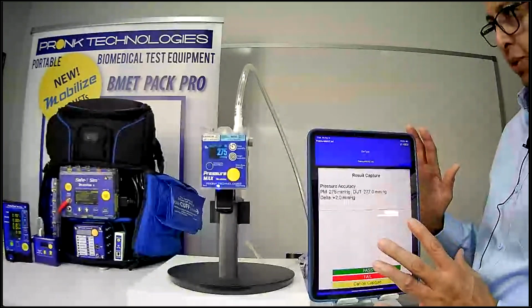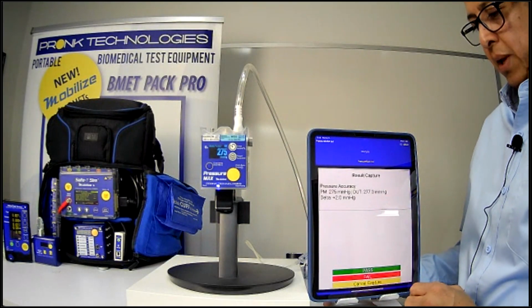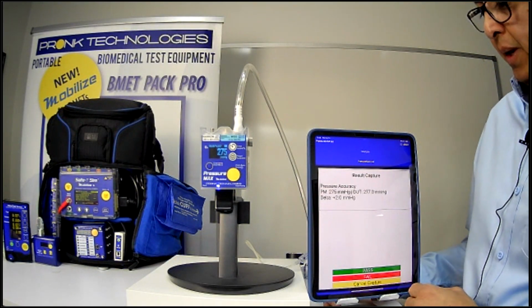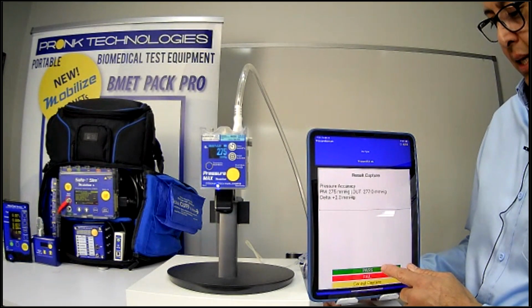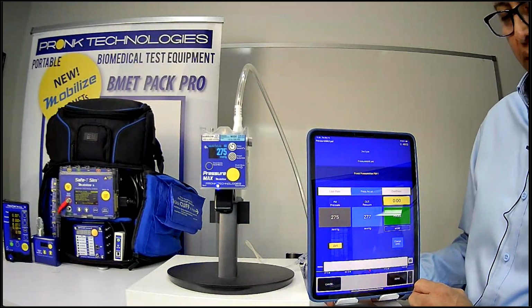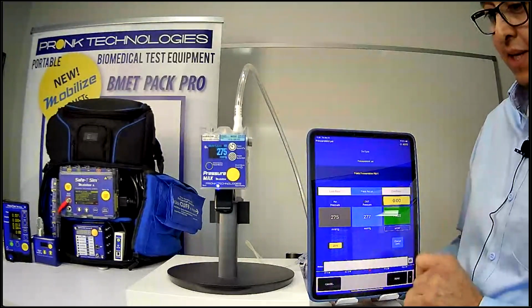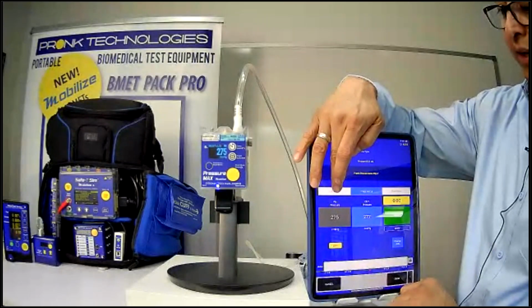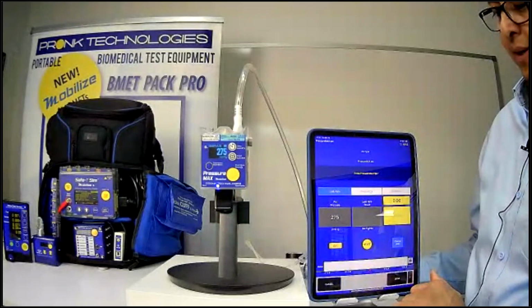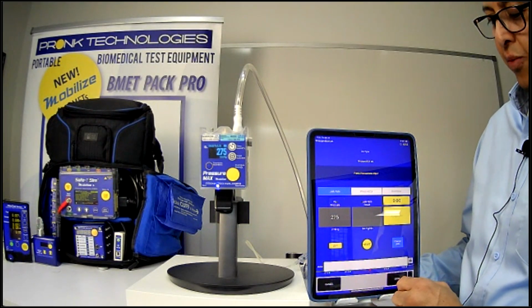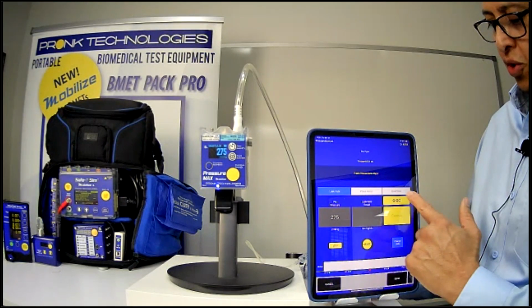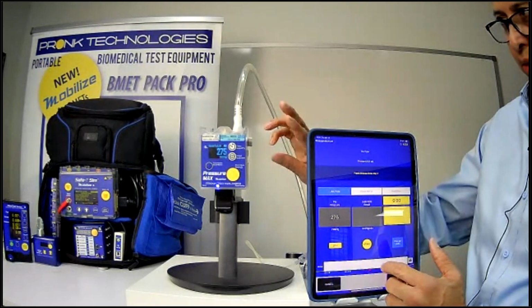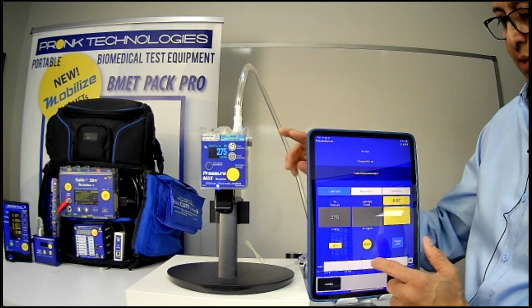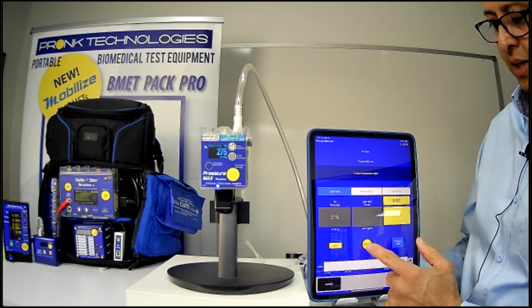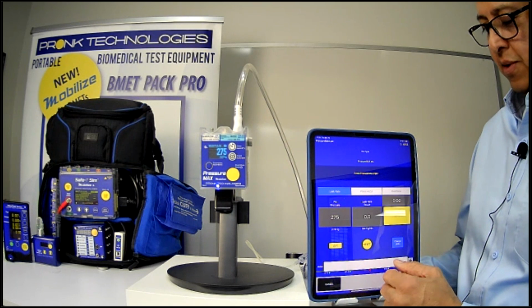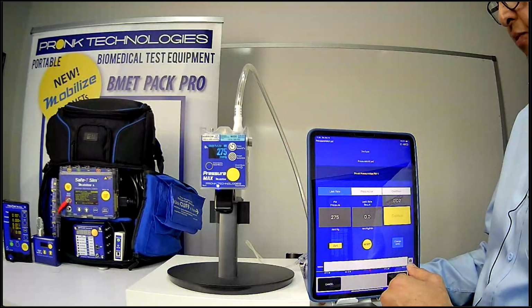So here, I'm able to do all the work I need to, utilizing the Pressure Max and capturing that data into the report itself. If I wanted to do a leak test, let's say I want to do a leak test, I go over to leak rate. I can inflate to the particular pressure I want, and then you can start the leak test here. So once you know your pressure is stabilized in the Pressure Max, a medical device, you have it connected, you can start the test here to start measuring a leak rate.